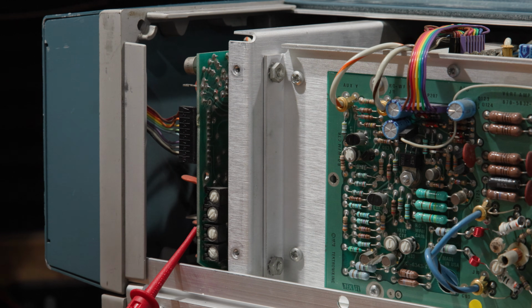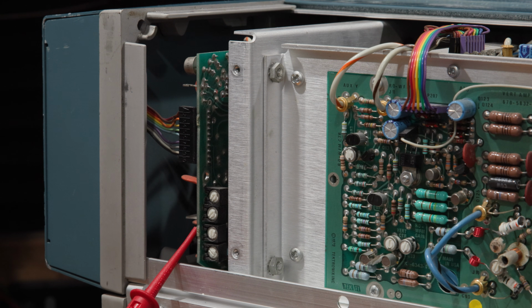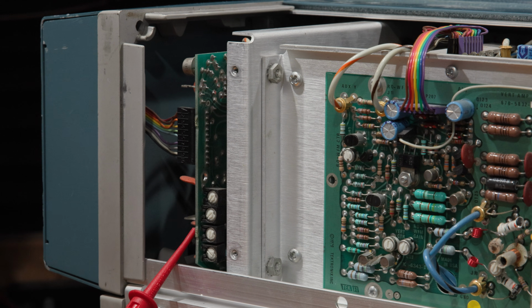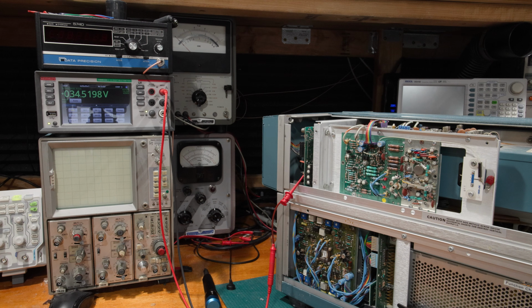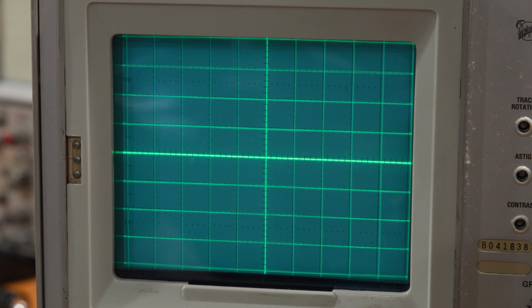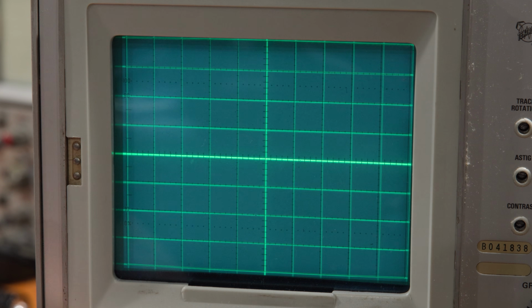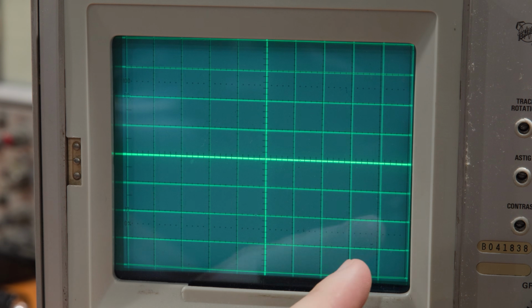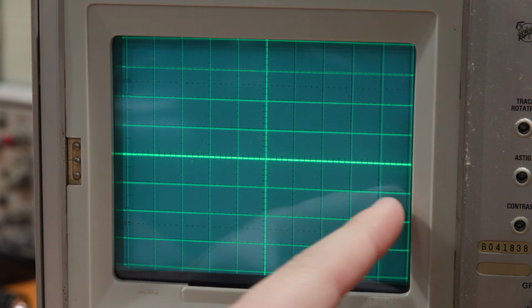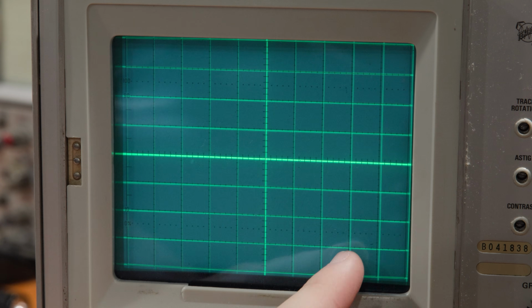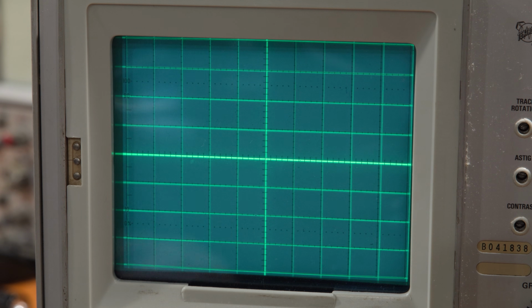Okay, after setting up the signal standardizers, which we'll take a look at here in a second, I had to crack the case open and high voltage case back open and hook up TP156. And with the power on, we should be reading 34 to 36 volts with focus control about mid-range. 34.5, so that's going to work quite well. Okay, we're supposed to grade the display by eye, and this is looking very good, although I'm seeing it shifting and we're seeing some bowing out here, so my geometry is off as well as my expansion on the display is off. So this is probably partially what's causing our inconsistencies with the digitizing section.